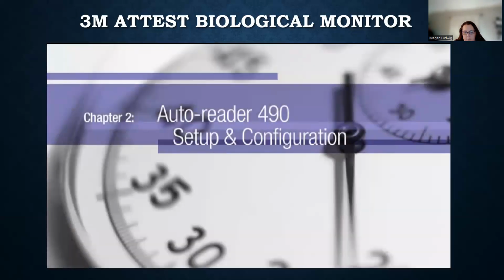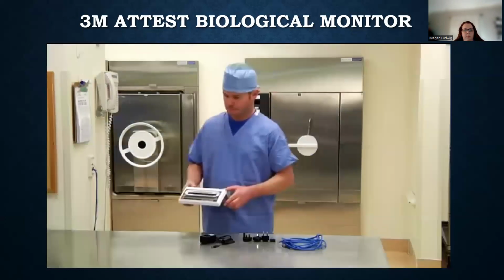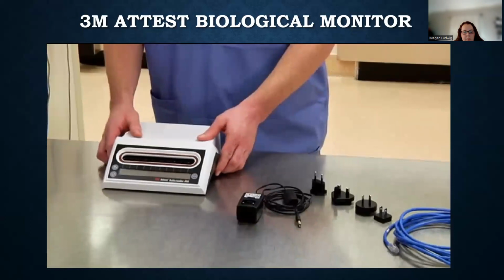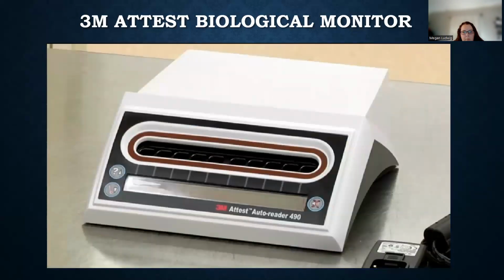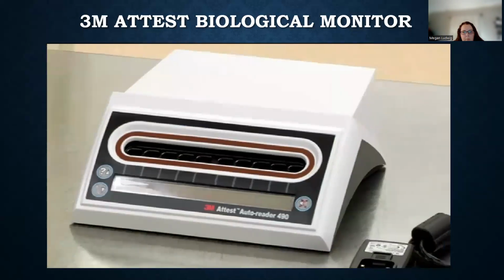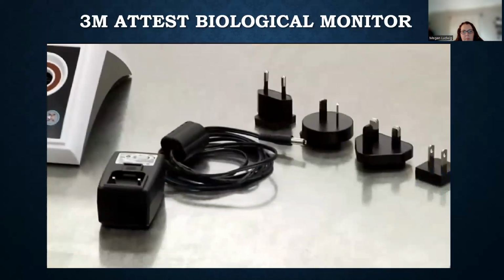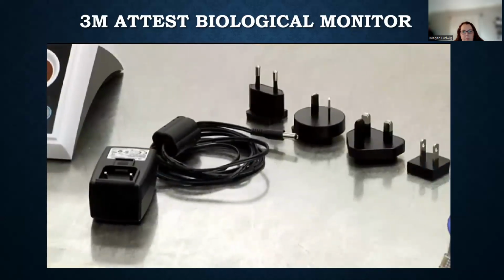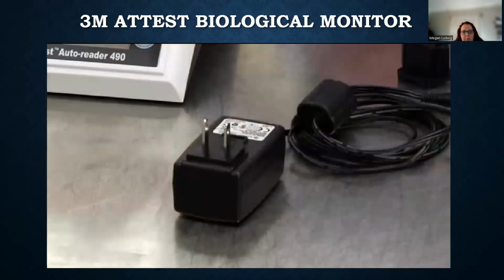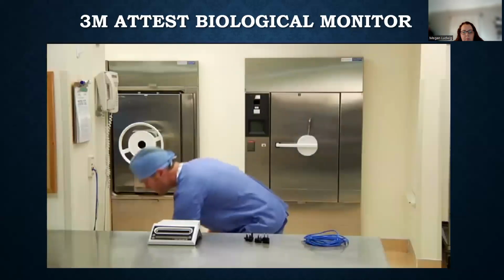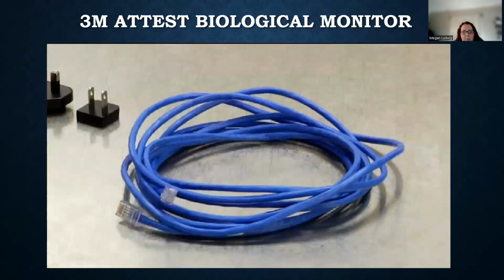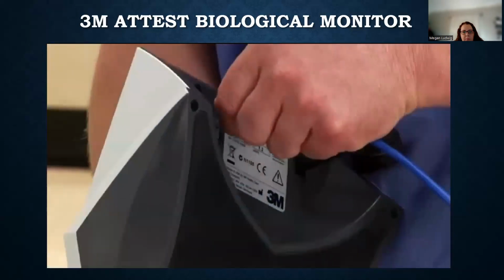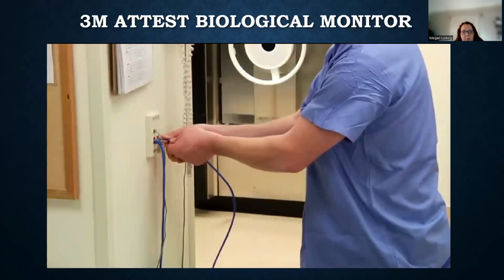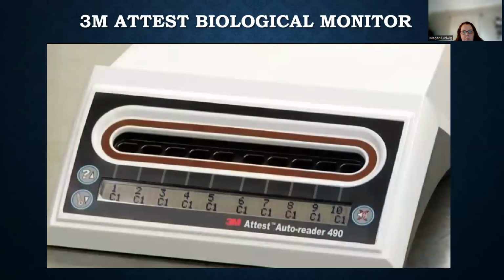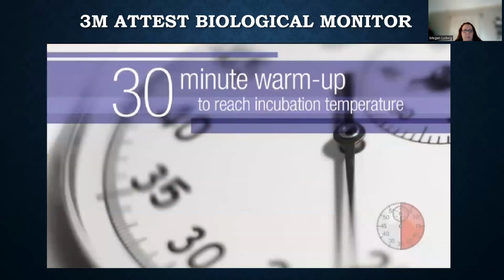Setting up and configuring your 3M Attest Auto-reader 490 is simple. First, place it on a firm, level surface near an outlet, away from sunlight and incandescent light. The Attest Auto-reader 490 comes with multiple power plugs for use in different countries. Select the plug appropriate for your country and insert it into an AC grounded outlet. If you plan to use the Attest web app, connect the supplied Ethernet cable to an Ethernet jack. Once the unit is plugged in, allow it to warm up for 30 minutes.